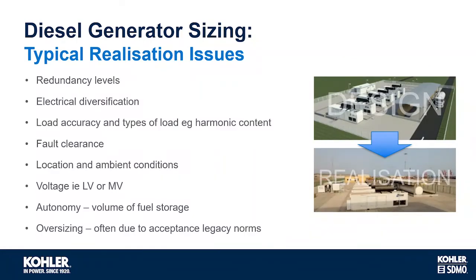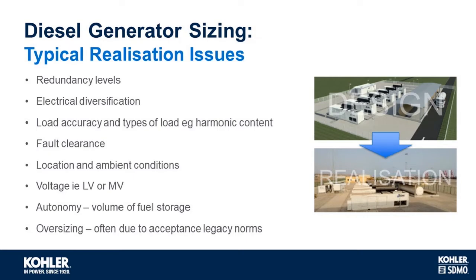So we've covered many considerations when sizing generators. Here are some other aspects of the design that need to be realized. So the redundancy levels, N+1, N+2, or even N+N. The electrical diversification, i.e. the diversified percentage of the total power required. The load accuracy, and the types of load, for example, is there any harmonic content? Does the generator set need to have any specific fault clearance capability? The location and ambient conditions.